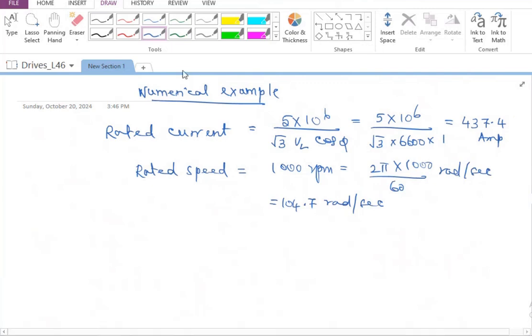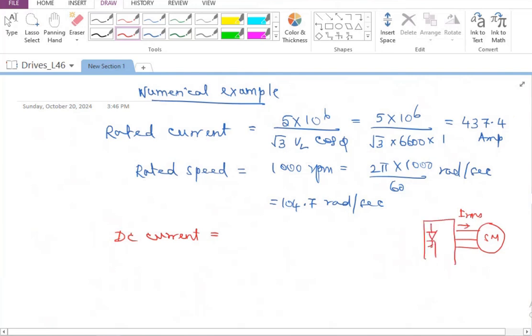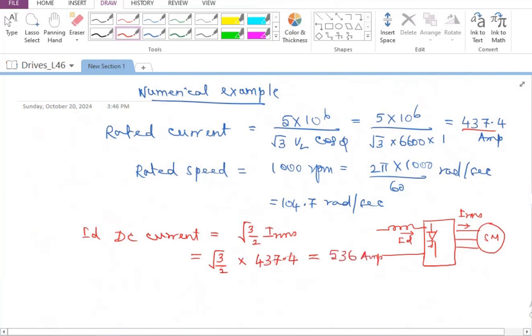Now, when you feed it from an LCI, the DC side current can be calculated as follows. This is the three-phase machine current going to the synchronous motor drive, which I'm calling IRMS. Whereas here I have the LCI connected, and I'm going to have the DC link current coming here, so this is the DC link current I'm talking about. So this DC current will be root of 3 divided by 2 times IRMS, because root of 2 by 3 ID is IRMS. We derived this earlier, so we should be able to calculate this. So this is root of 3 divided by 2 multiplied by IRMS, which we calculated as 437.4 ampere. So this comes out to be 536 ampere.